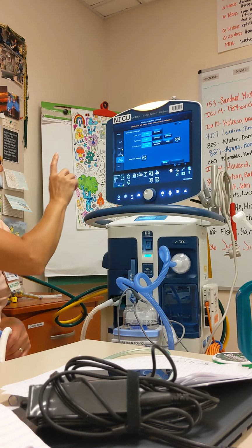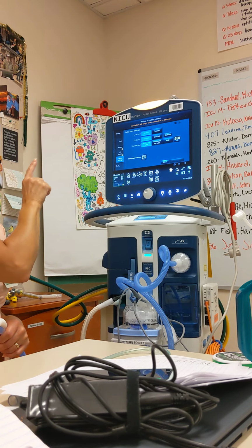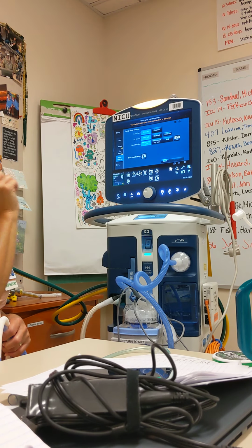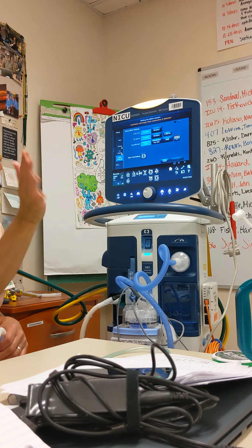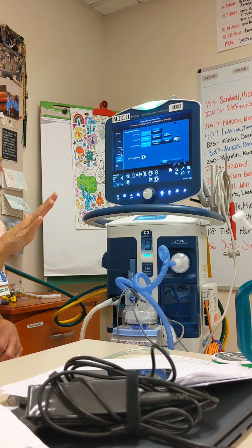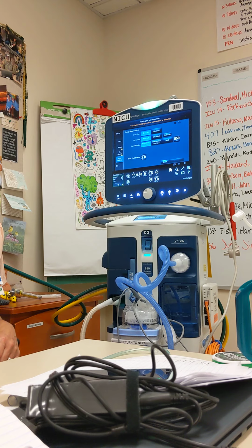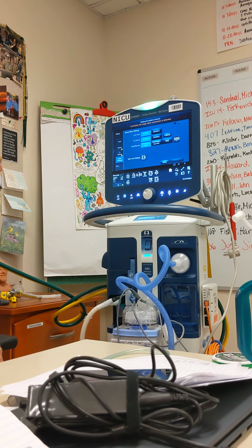Got it. Leak sync: enabled. Yeah, and leak sync will now automatically enable when you hit non-invasive. Okay. So you should never need to re-enable it. It should automatically be there. So we just have to make sure that that's at 550. 550, yeah.